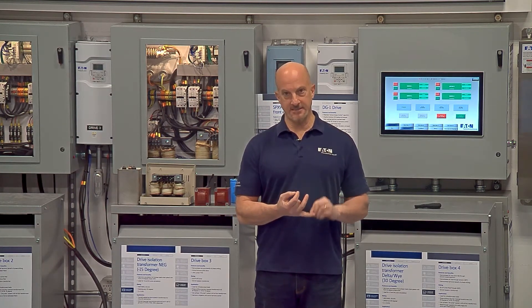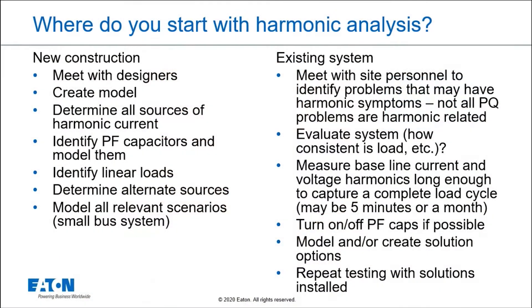So are we looking at an existing system or new construction? If it's new construction, the first step is probably to meet with the designers and make sure you understand what the goal of the design is — to reduce or minimize harmonics. Then you want to create a model and determine all of the sources of harmonic current that could occur.